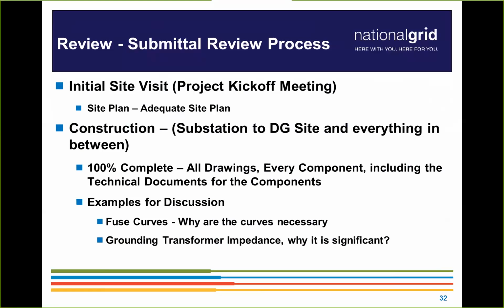And the reason being is because we have to take, for instance, fuse curves, or if you have some kind of a breaker or automated device, we have to take the curve characteristics of that device and coordinate that with other devices on our circuits. So having the specific curves for a fuse or specific settings or curve values for a breaker or some other device is very critical and essential for us to complete our design review and model that with a coordination study with our circuits. So that's why those types of elements, for instance, the fuse curves, are important.